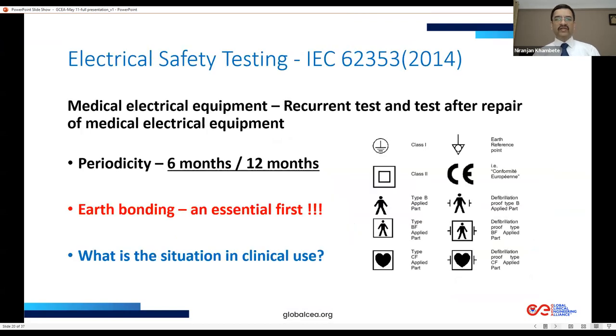We all know electrical safety testing is guided by an international standard, IEC 62353, which is also adopted in India as an Indian standard. The title of the standard is: medical electrical equipment, recurrent test and test after repair of medical electrical equipment. Typically, clinical engineers do electrical safety testing periodically, either once in 6 months or once in 12 months.